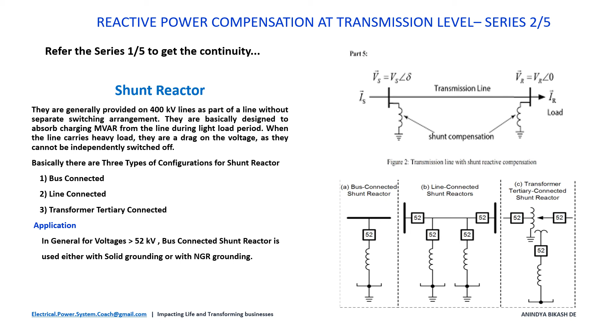Other than shunt compensation through inductive compensation, there is capacitive compensation. So shunt capacitors are used, and they can be used in series and parallel combination even up to 400 kV. The main disadvantage of this shunt compensation is that whenever the requirement is there to satisfy the reactive power support in the system, it is not capable of delivering, because the reactive power output from these capacitor bank units is proportional to the square of the applied voltage.